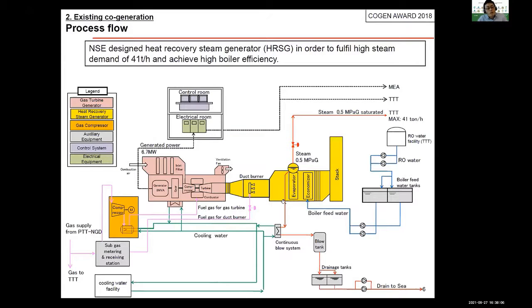In this slide, I'm showing the schematic process flow. Basically, this cogeneration plant consists mainly of a gas turbine and a heat recovery steam generator equipped with a duct burner. In order to achieve high efficiency of the plant, the heat recovery steam generator is key because cogeneration is a technology to make maximum use of waste heat. And to be honest, we cannot control gas turbine efficiency, but we can control the efficiency of the HRSG.